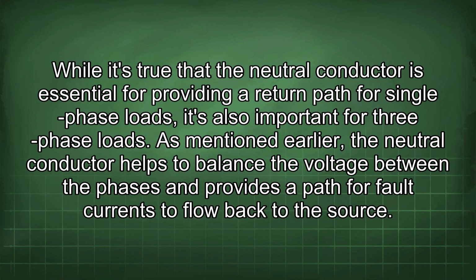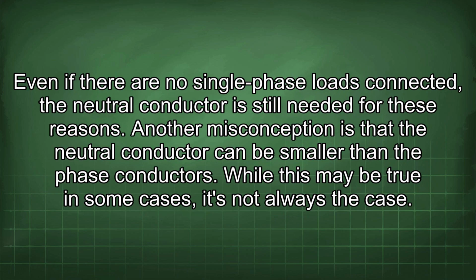While it's true that the neutral conductor is essential for providing a return path for single-phase loads, it's also important for three-phase loads. As mentioned earlier, the neutral conductor helps to balance the voltage between the phases and provides a path for fault currents to flow back to the source. Even if there are no single-phase loads connected, the neutral conductor is still needed for these reasons. Another misconception is that the neutral conductor can be smaller than the phase conductors. While this may be true in some cases, it's not always the case.